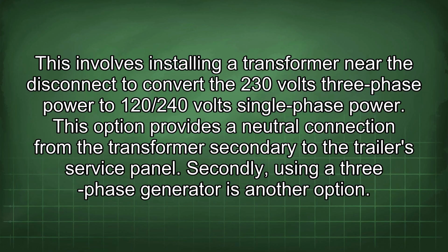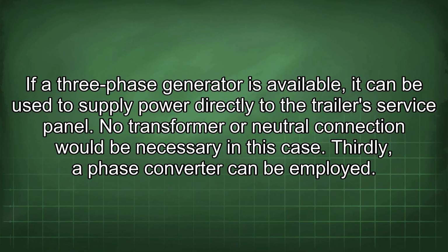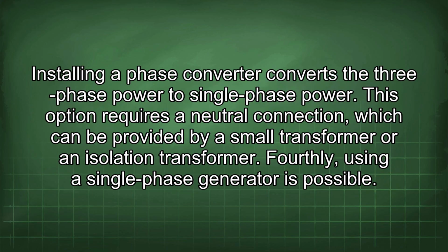Secondly, using a three-phase generator is another option. If a three-phase generator is available, it can be used to supply power directly to the trailer's service panel. No transformer or neutral connection would be necessary in this case. Thirdly, a phase converter can be employed. Installing a phase converter converts the three-phase power to single-phase power. This option requires a neutral connection, which can be provided by a small transformer or an isolation transformer.